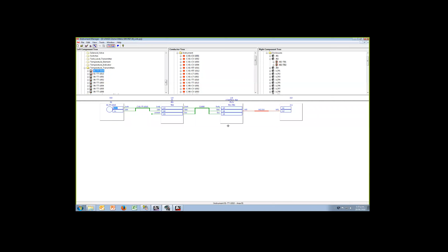Let's now look in our connection view - this is how we connect our items together. If we look in our pressure transmitters, there's a pressure transmitter we created before with its cable. In the middle we have conductors, panel wires or cables, and there's our instrument cable. You can look at the individual conductors and see how each wire is connected.